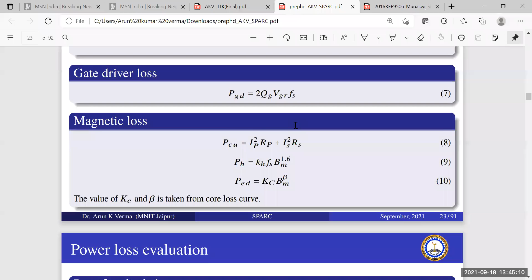Magnetic losses, that is eddy current losses and hysteresis losses. Then ultimately you have the total losses. Copper losses, I square R: IP square RP is the copper loss in the primary, and I square RS is the copper loss in the secondary. And these are the hysteresis and eddy current losses. Kc and the value of beta can be taken from the core loss curve, which is also given in the data sheet, because you are using a certain core, E core, S core, or a lot of cores are available. That depends upon how you design the circuit, how you design the transformer.